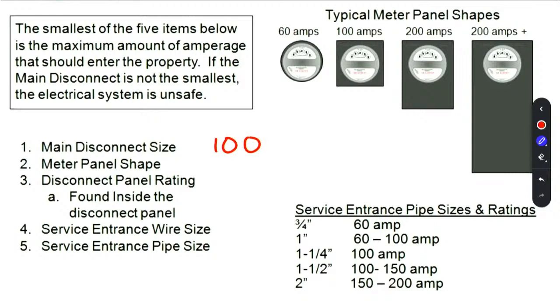The next one is going to be the meter panel shape. We're not going to be able to get access to the inside to see the data plate of these meters, so we're really not going to know for sure. This is nothing but a rule of thumb. It's not black and white, not guaranteed like it's written on there, but it's still a pretty good rule of thumb. In our areas, I also want you to assume these could actually be 30 amps. It's common that these are 60.